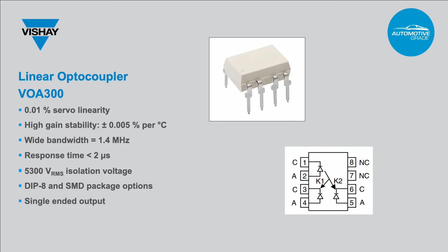Okay, finally jumping back to the rest of the details on the current sense feedback. I mentioned a comparator circuit that was used to detect an overcurrent situation. Once the amplified current sense voltage, highlighted in the red box in the top left corner of the schematic, has passed through the linear optocoupler across the isolation barrier, it is continuously compared to a preset reference voltage that corresponds to an overcurrent event. When this level is exceeded, the comparator trips and an overcurrent signal is sent to a microprocessor interrupt, and the main load switches are immediately opened.